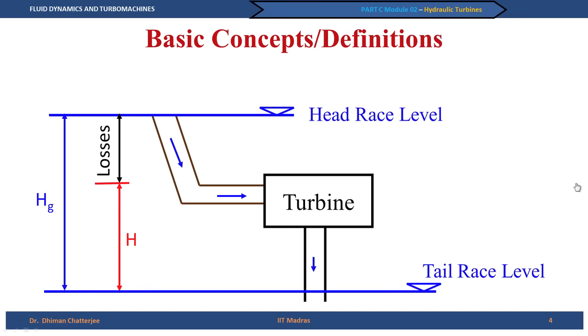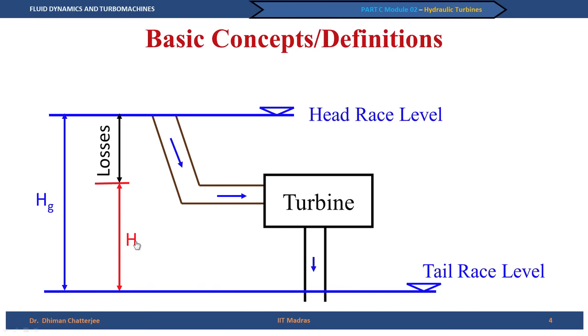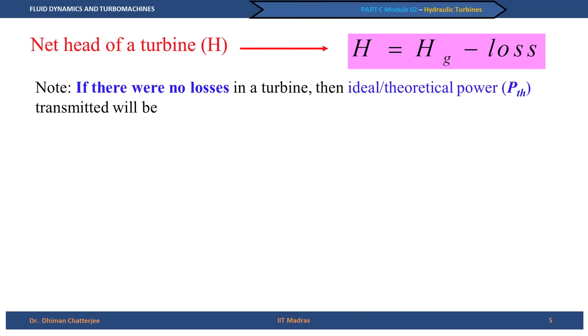The difference between the two is accounted for by the losses. Whenever we discuss the head utilized by the turbine, unless specifically mentioned, we always refer to the net head H. Thus we can say that net head H equals H_G minus losses. And if we assume an idealized machine with no losses, the theoretical power transmitted is P_theoretical = ρ V̇ g H.